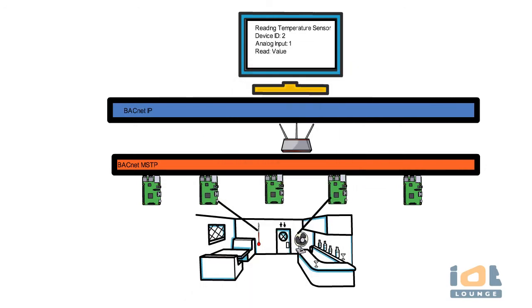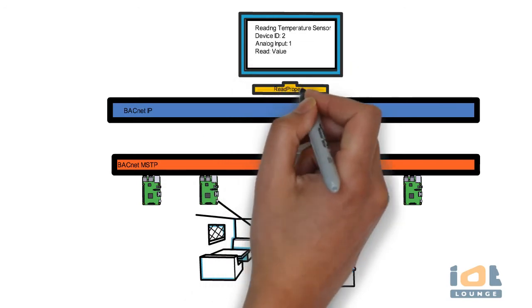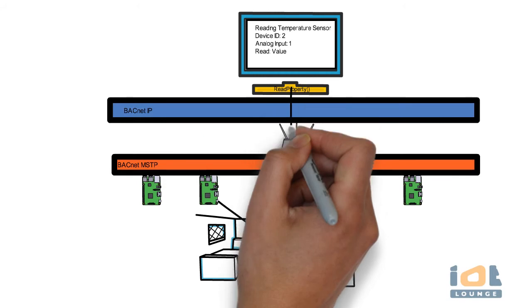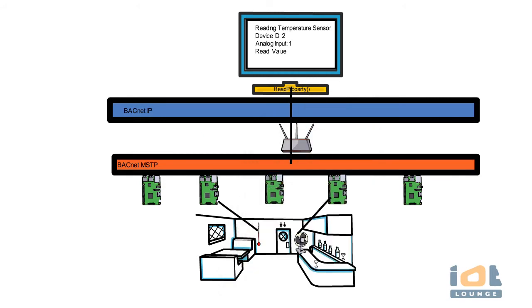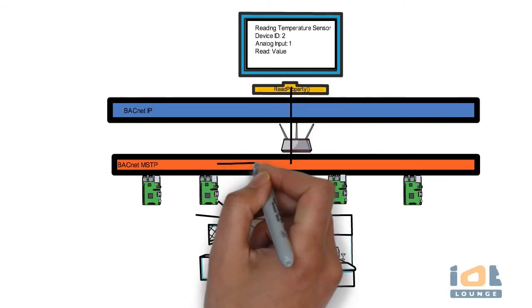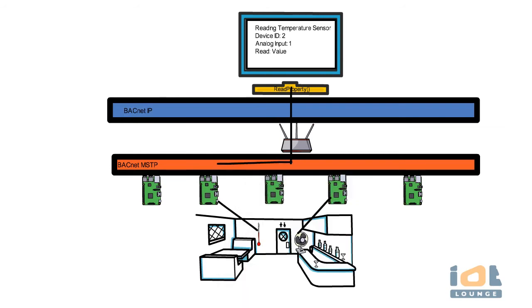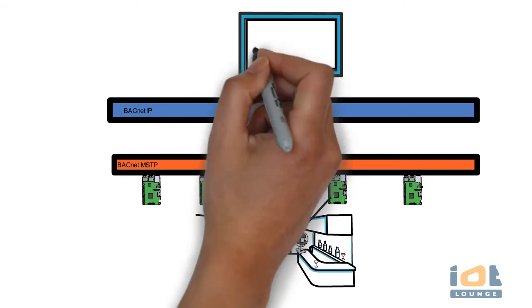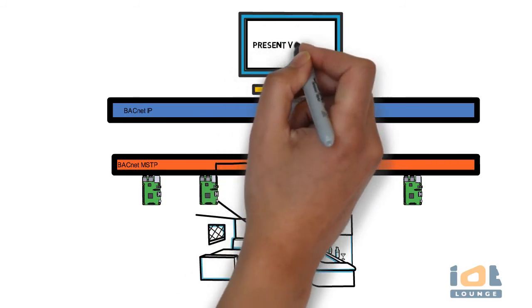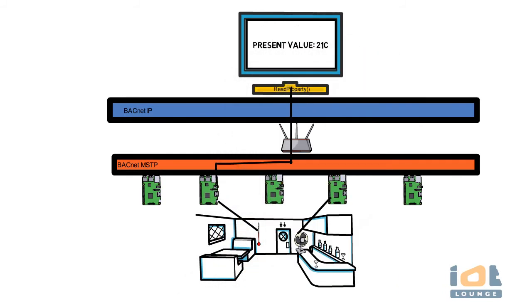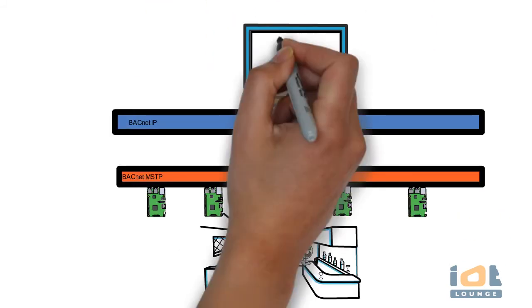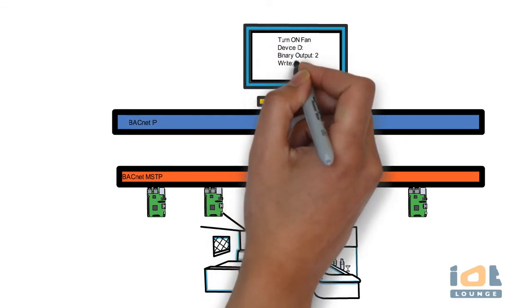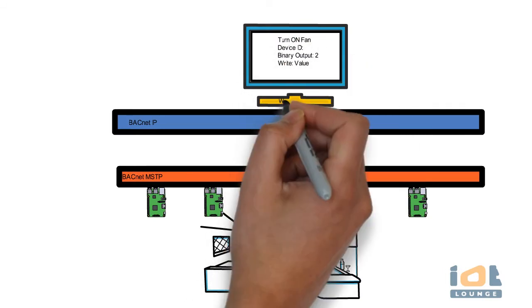For example, to read current temperature from a temperature sensor in a building, the user selects the device and the analog input which the sensor is connected from the enterprise BACnet software. The protocol sends a read property service targeting the selected device. The packet traverses between the IP and MSTP layer via the router to the destination device. The device responds back with the current temperature value. The value is displayed in the software for users' visibility.